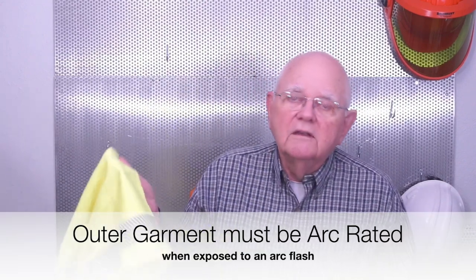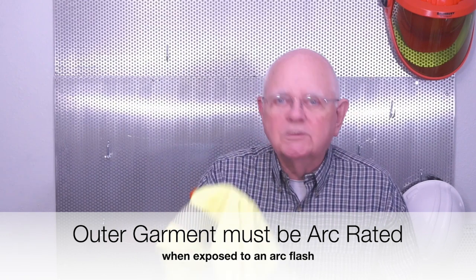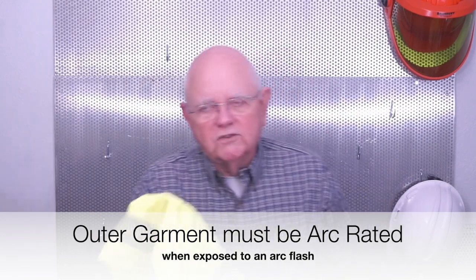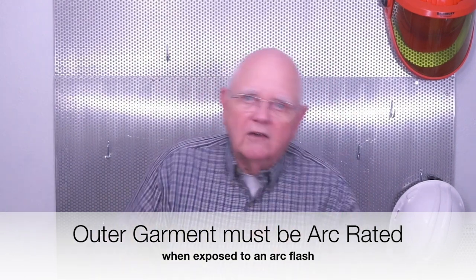So, PPE category method. Let's say I have to wear some Category 3 clothing rated for 25 calories. However, this vest is only rated for 9.6. That's okay. I can still wear my 25 cal coveralls or whatever it is, and then I can put on my 9.6 calorie vest over that. If I'm in an arc flash, this guy's destroyed. That's okay. Its purpose is not to protect my skin from burn injury. That's the 25 cal coveralls or whatever I'm wearing.